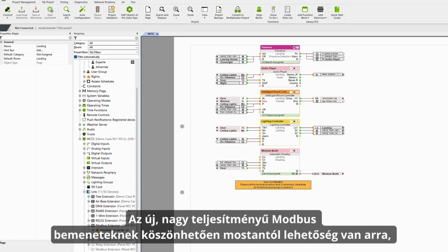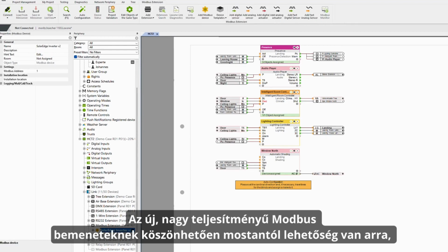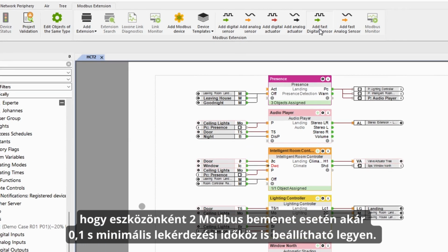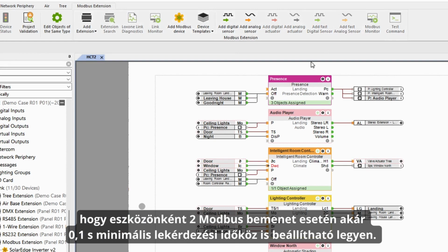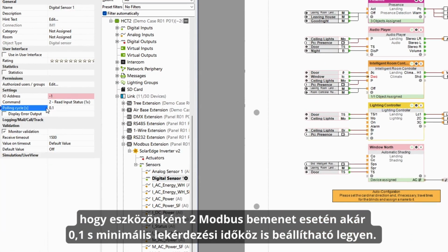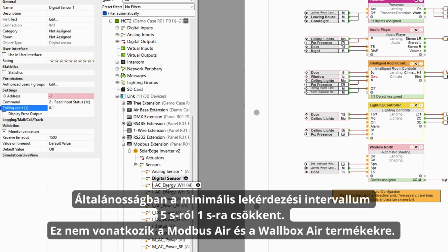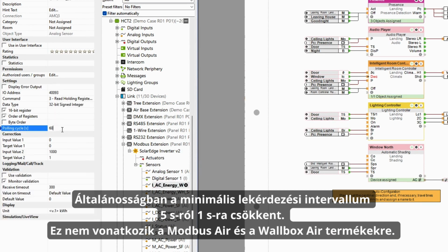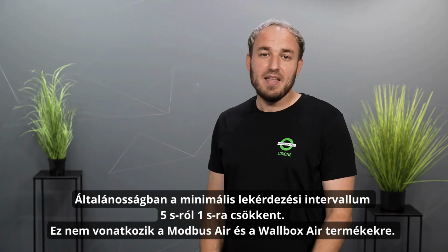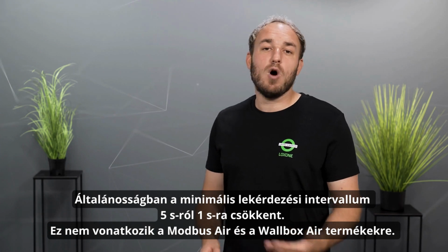Thanks to the new Modbus high-performance inputs, it is now possible to set a minimum query interval of up to 0.1 seconds with 2 Modbus inputs per device. In general, the minimum query interval has been reduced from 5 seconds to 1 second. The Air products, Modbus Air and the Wallbox Air, are excluded from this feature.